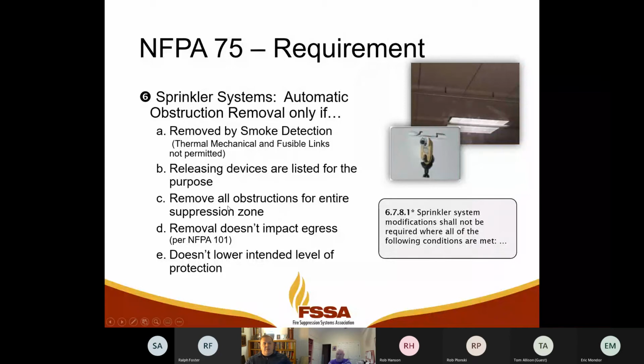Third here on the list, remove all obstructions for the entire suppression zone. So that basically means that if you're going to drop the curtains, you're not just going to drop it on one hot aisle way. You're going to drop it on all of them. Okay. Fourth, the removal shouldn't impact egress. Okay. So as I need to exit the room, I don't need to be jumping over piles of curtains or getting hit in the head with them as they're dropping.